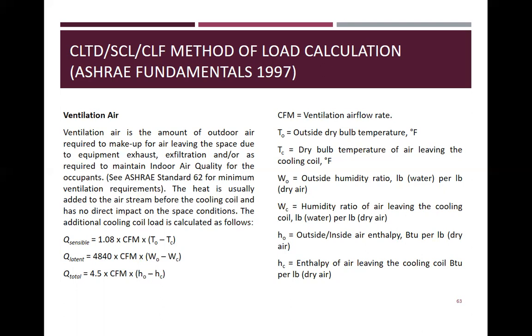H sub O is equal to outside air enthalpy. H sub C is equal to enthalpy of air leaving the cooling coil, BTU per pound. Wait, I'll remove this inside.